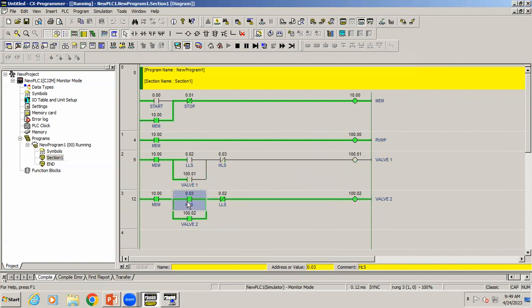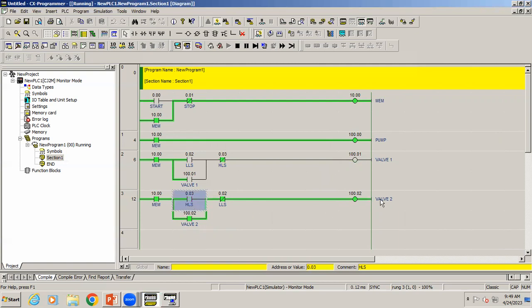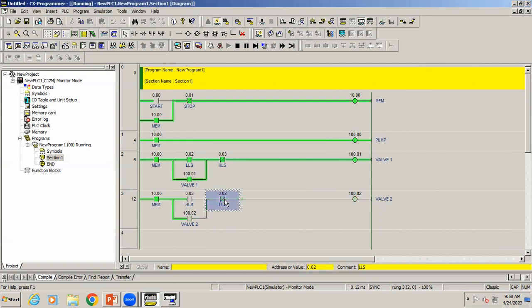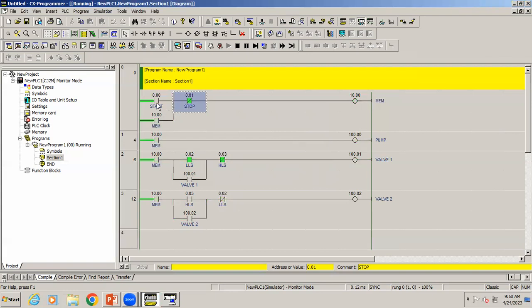Once the level drops below the high level sensor again, it would normally trip the valve — that's why we use latching. Even if the sensor turns OFF, due to the latch the valve remains open until the low level sensor is ON again. You can see the process keeps oscillating between low level and high level. I hope you understood how to use the latching concept. The parallel output address can be used in different positions depending on your logic. Now if you want to stop the process, press the stop push button — all outputs will turn OFF. Release it, then press start again to restart.